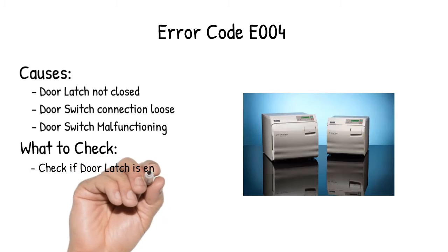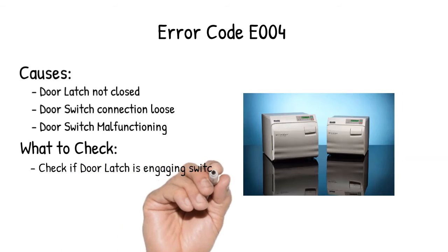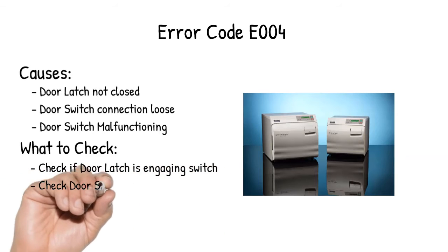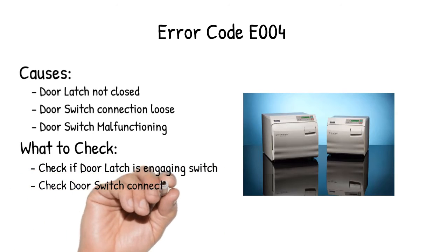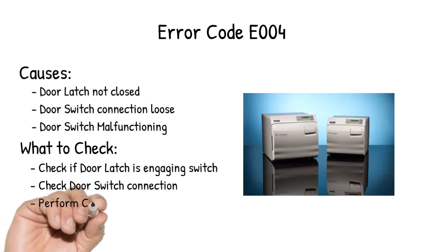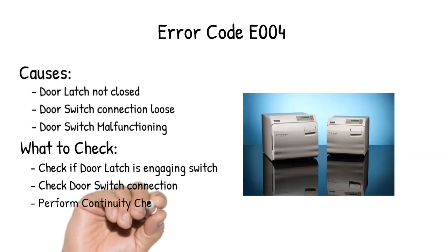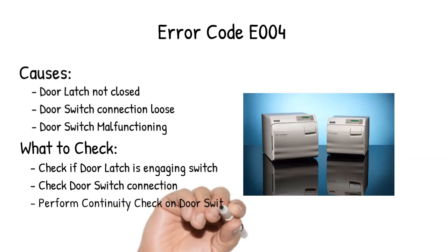Check if door latch is engaging switch, check door switch connection, perform continuity check on door switch, normally open.